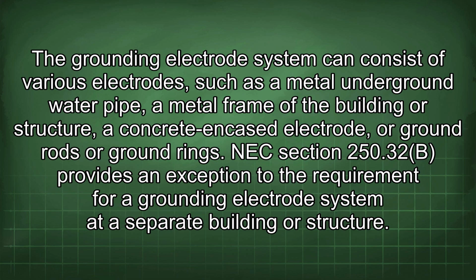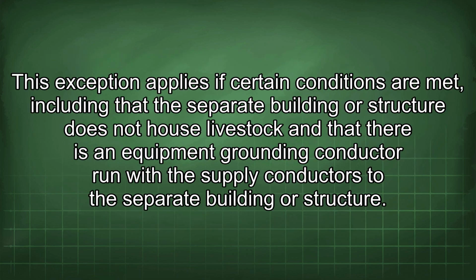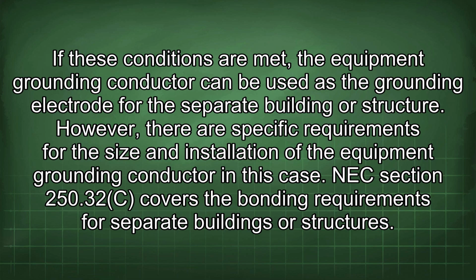NEC Section 250.32b provides an exception to the requirement for a grounding electrode system at a separate building or structure. This exception applies if certain conditions are met, including that the separate building or structure does not house livestock and that there is an equipment grounding conductor run with the supply conductors to the separate building or structure. If these conditions are met, the equipment grounding conductor can be used as the grounding electrode for the separate building or structure. However, there are specific requirements for the size and installation of the equipment grounding conductor in this case.